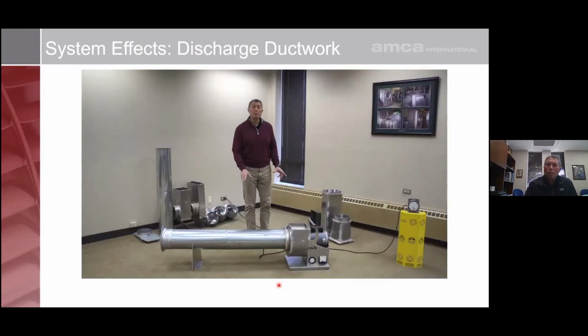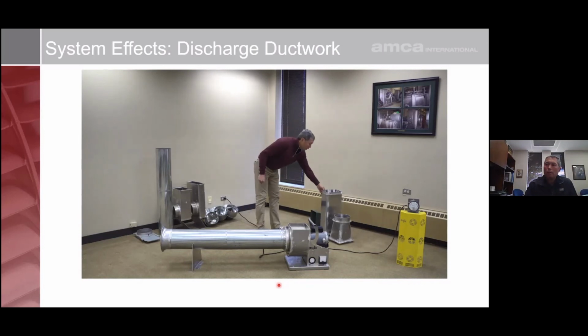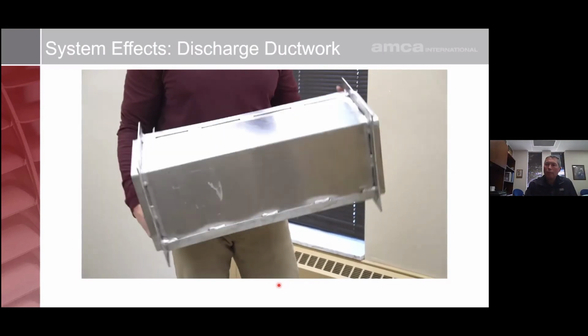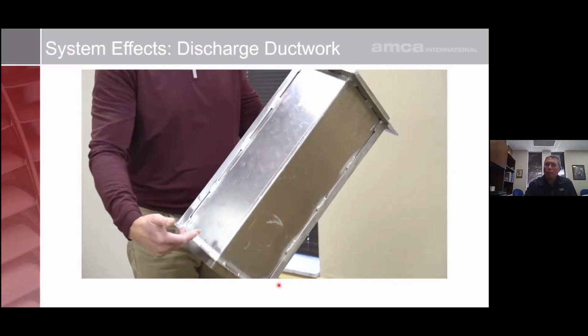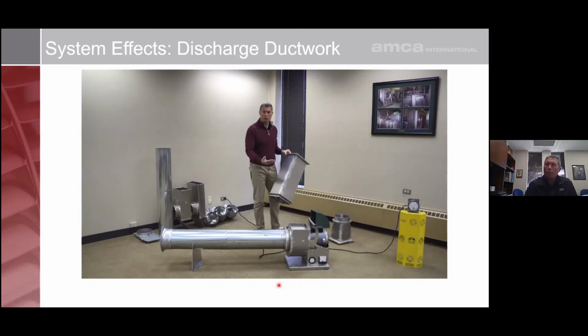As you can see here, we've moved the measuring device, the pitot tube, to the inlet of the fan, and we're going to measure or examine how fan performance changes when we add or change the ductwork configuration on the discharge side of the fan. So the first thing we're going to do is add a straight run of ductwork to the fan. The straight run of ductwork allows for the velocity profile to even out as the air discharges the fan.